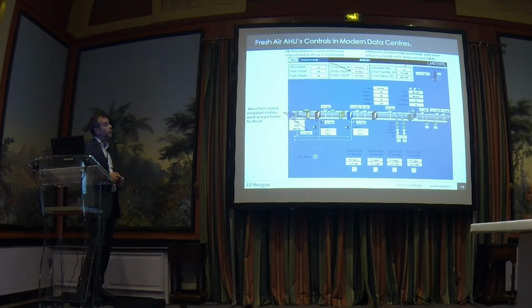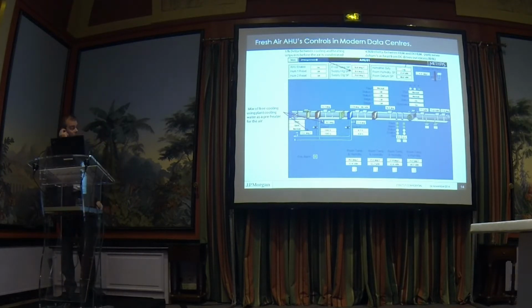So, a 17K delta between heating and cooling. If the air coming out of that tube goes below 8, I'll start heating it with electrics. If the supply temperature coming out of there goes above 25, I'll start cooling. So most times of the year, the air conditioner's not doing anything regarding heating or cooling.